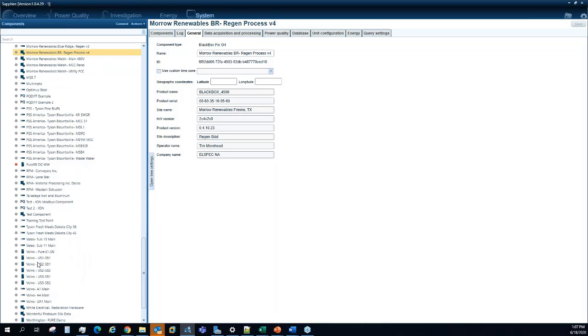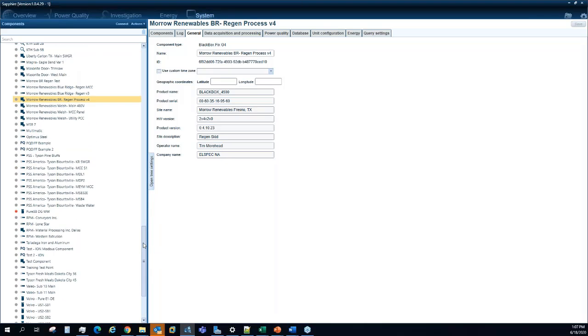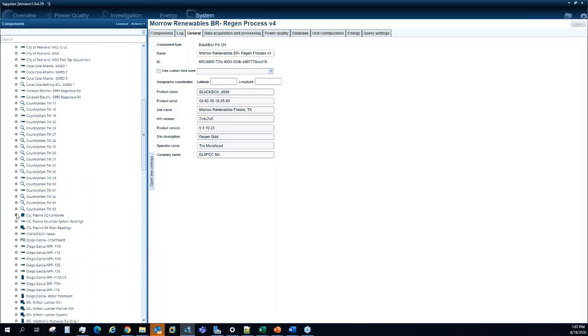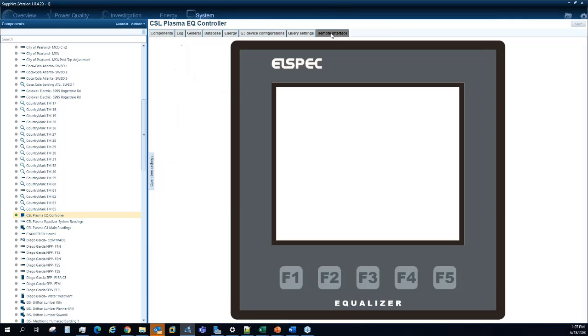you can actually access the controller remotely. So where was this? Here's an example. It's one that I set up. I'm not actually live connected to it right now, but if this was connected, we would actually see exactly what's on the controller and remotely, and we can actually change parameters. We can view system logs, which adds another layer of remote diagnostics capabilities. Because, as we all know, people oftentimes don't have the time to go check around and ensure that things are running. They're just expecting it to.